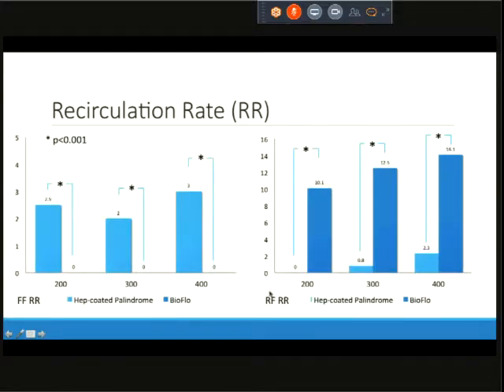So here's the result of the recirculation rate study. First, the graph is demonstrating the forward flow recirculation rate and comparing the palindrome versus the bioflow. And as you can see, the bioflow had a 0 recirculation rate in all three different flow rates at 200, 300, and 400 milliliters per minute. Again, significantly different from the palindrome groups, which demonstrates how efficient the dialysis system is for the bioflow.